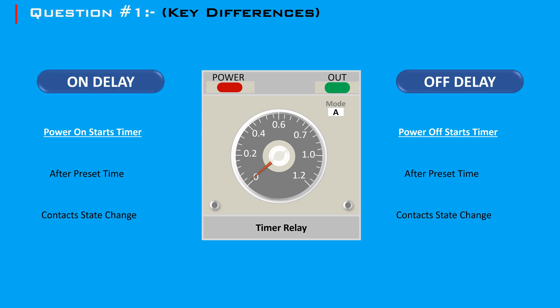The key differences between on-delay and off-delay timers are: On-delay timer delays turning on and requires an input signal to start the timer. Off-delay timer delays turning off and requires the removal of the input signal to start the timer.